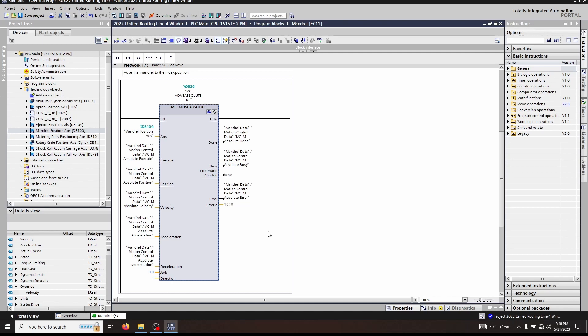If you're not familiar with the MC_Home function, please watch the video that I've done about that function. As with all motion control axes, you will need the MC_Power, MC_Reset, and MC_Halt. MC_Power turns on the axis, MC_Reset clears any faults, and MC_Halt stops the axis if there is any undesired motion.